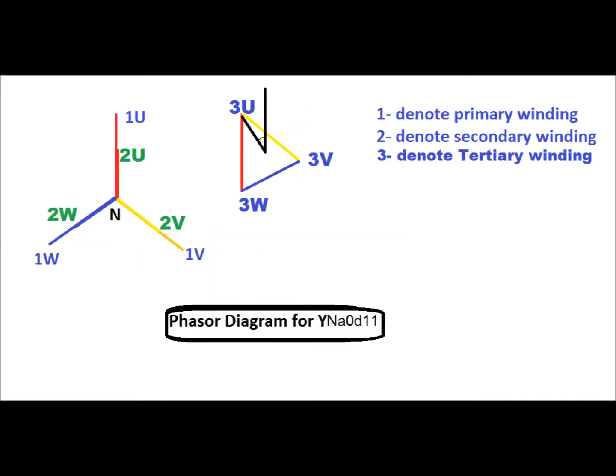The vector diagram for YNA0D11 is shown in this diagram. Here 1 denotes primary winding, 2 denotes secondary winding or LV winding, and 3 denotes tertiary or TV winding. 1U, 1V, and 1W denote red, yellow, and blue phase of the primary winding. 3U, 3V, and 3W denote red, yellow, and blue phase of the tertiary winding. Primary and secondary windings are in phase, while tertiary winding leads by 30 degrees with the primary winding.